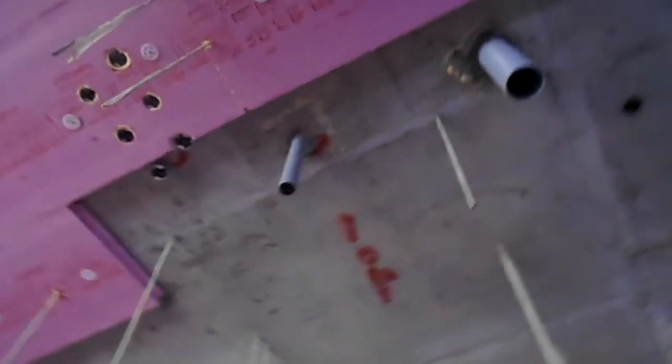Whichever we installed in the slab, we need to check if the circuits are open or blocked by concrete. So that is very important you have to check. And if it is all cleared or there is some blockage, what you need to do? GI conduit, because we are doing the open work, so GI conduit is required. Because it is not allowed PVC conduit, GI conduit is allowed for open work, so as we did here.